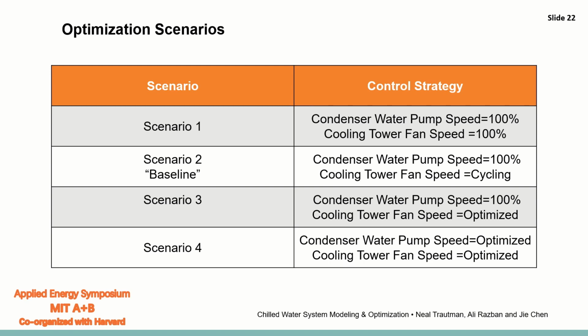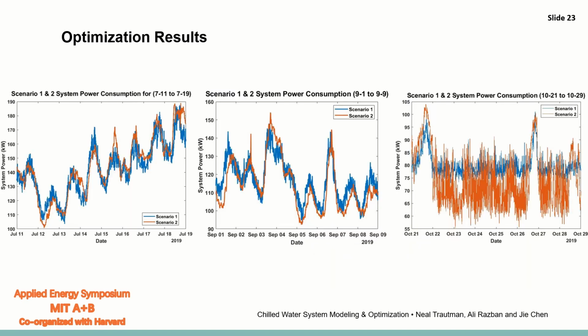Scenario three, we decided that the condenser water pump speed would run at 100%, while the cooling tower fan speed would be optimized with the optimization algorithm. And finally, in scenario four, we decided to optimize both the condenser water pump speed and the cooling tower fan speed in order to try and minimize the total system power even further.